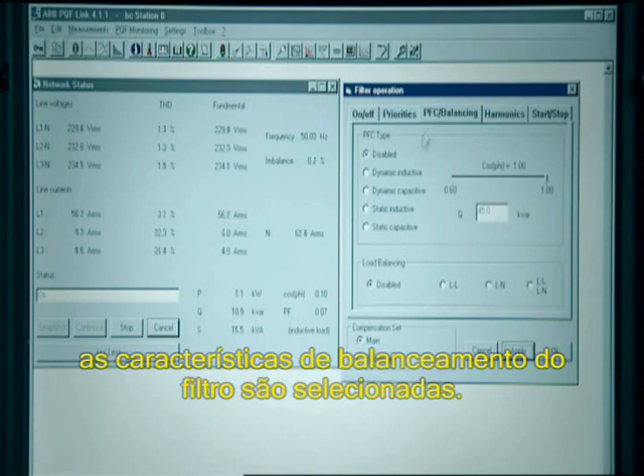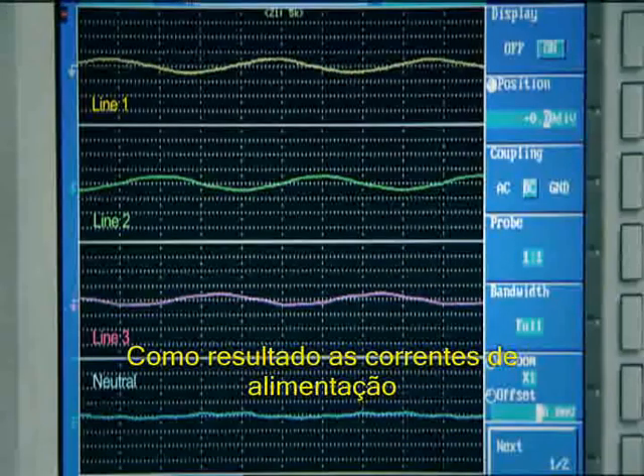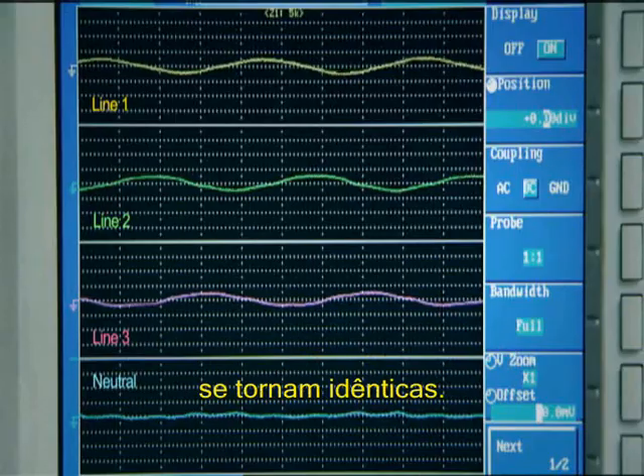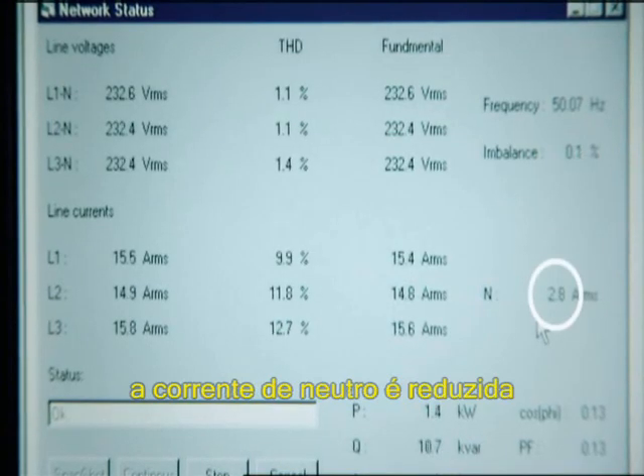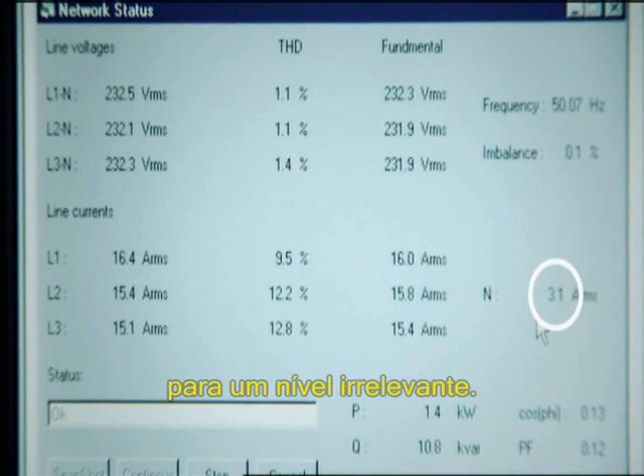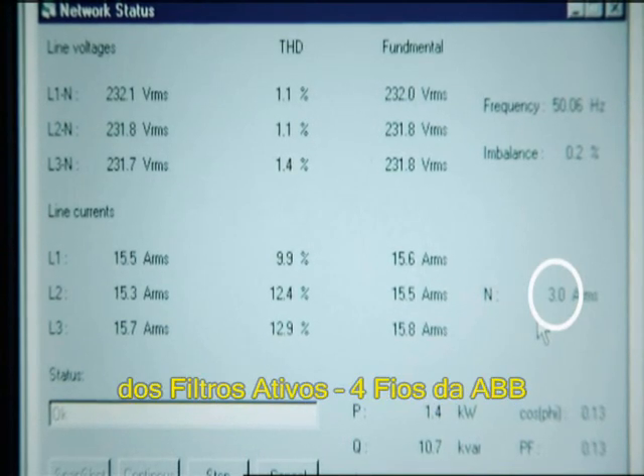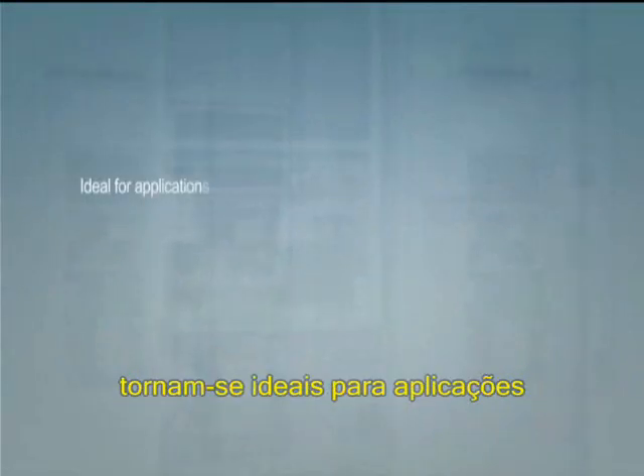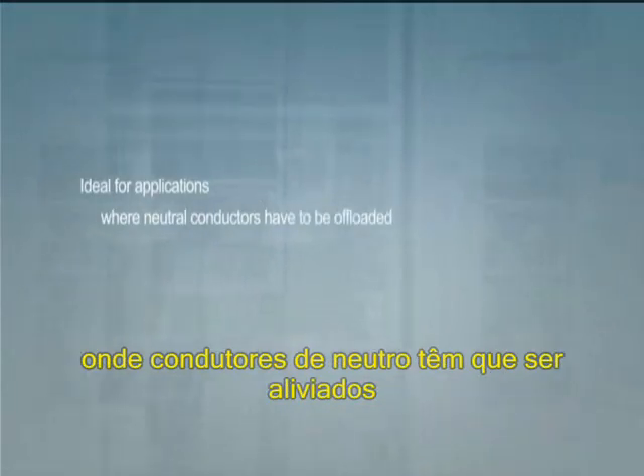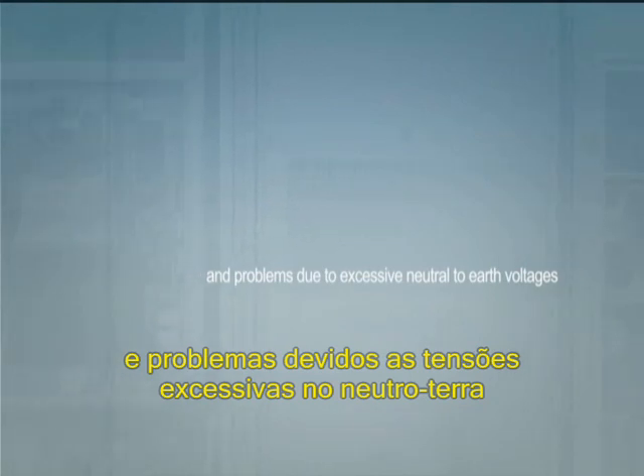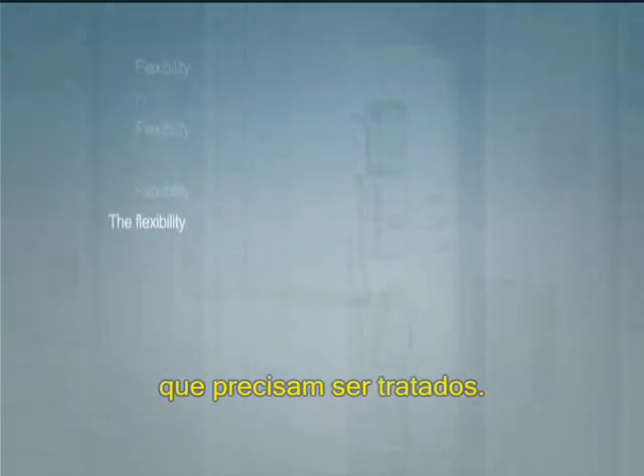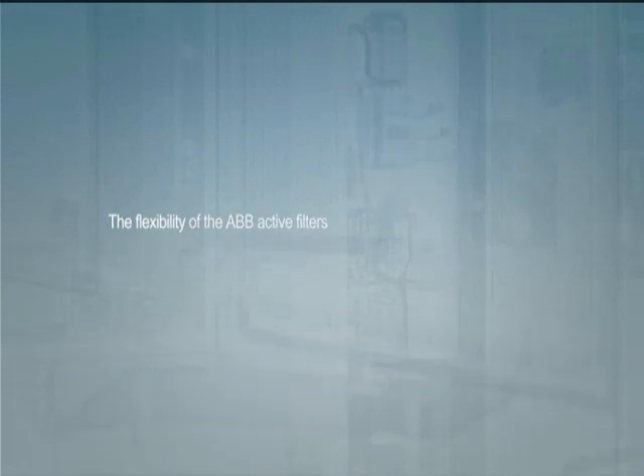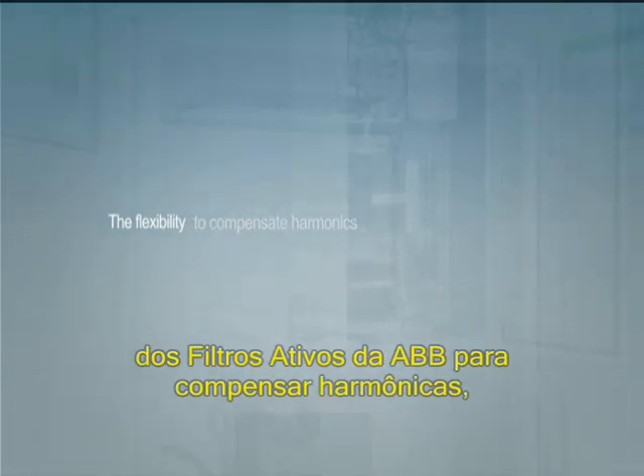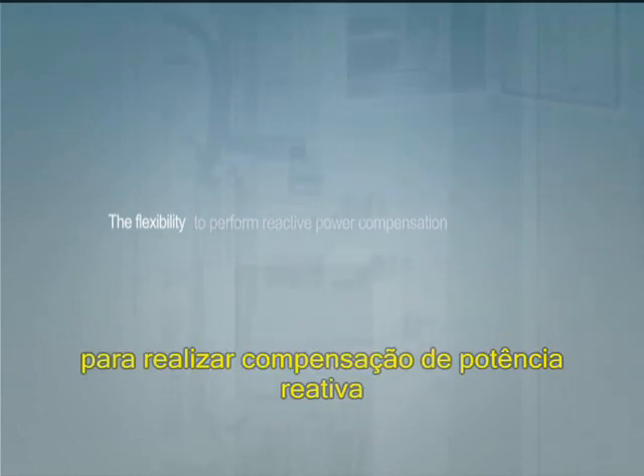As a next step, the filter's balancing features are selected. This results in the supply currents becoming virtually identical. At the same time, the neutral current is reduced to a negligible level. This feature of the ABB 4-wire active filters makes them ideal for applications where neutral conductors have to be offloaded and problems due to excessive neutral-to-earth voltages have to be addressed. These demonstrations clearly illustrate the flexibility of the ABB active filters to compensate harmonics, perform reactive power compensation, and balance loads. But the PQF has much more to offer.